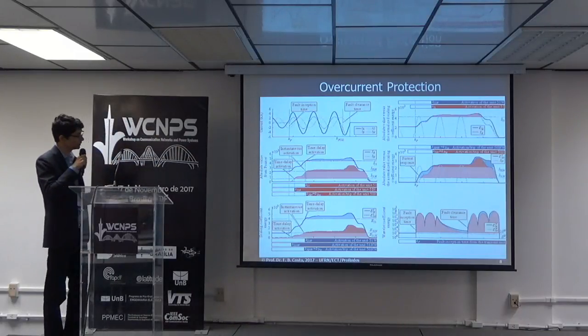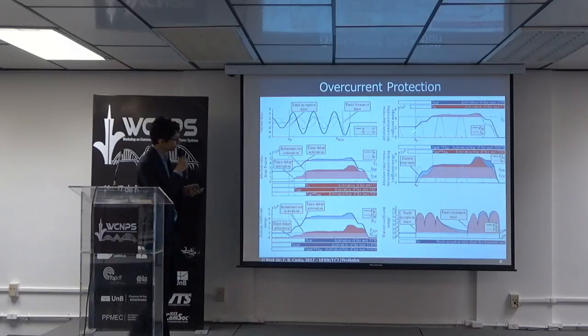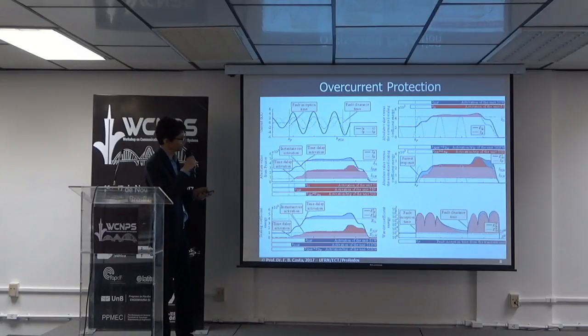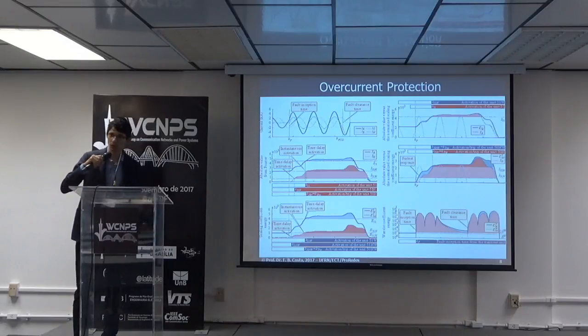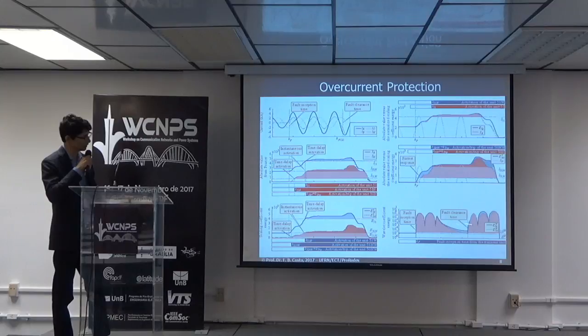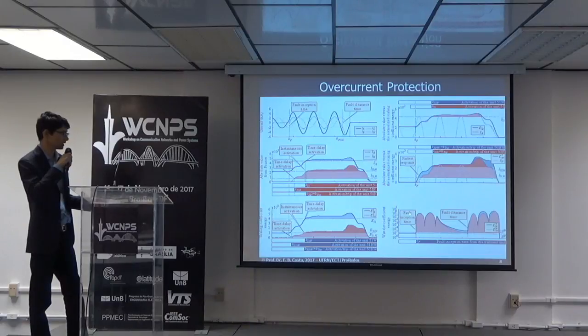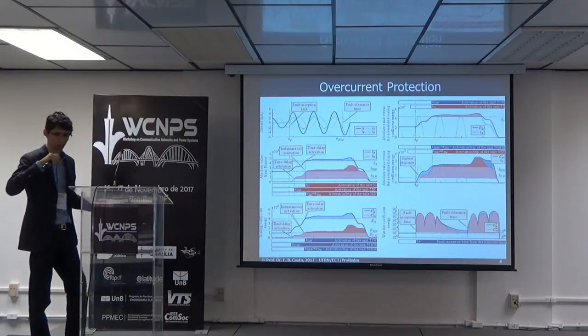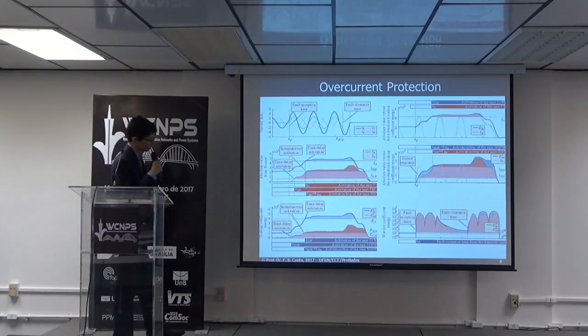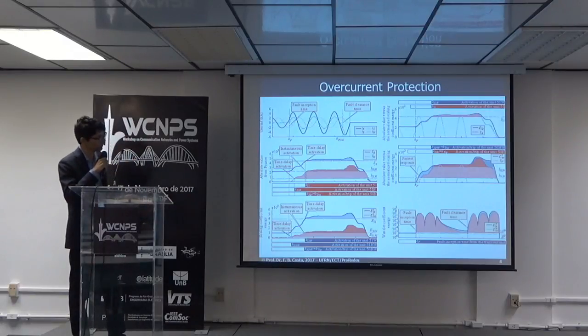Here we have the comparison of the performance, phase and neutral units, and the wavelet and the Fourier answers are similar. However, the wavelet was a little bit faster, but the general features were the same. However, the wavelet transform has additional information that the conventional protection based on Fourier does not have. By using the wavelet transform, you have almost instantaneous fault detection, and we have the fault classification, sometimes the fault location. So this information can be useful in order to accelerate the overcurrent protection.